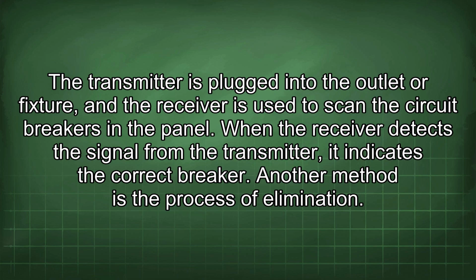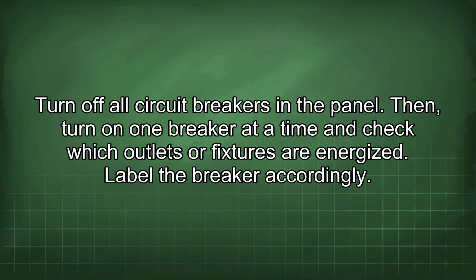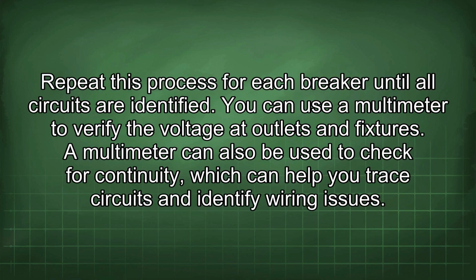Another method is the process of elimination. Turn off all circuit breakers in the panel. Then turn on one breaker at a time and check which outlets or fixtures are energized. Label the breaker accordingly. Repeat this process for each breaker until all circuits are identified. You can use a multimeter to verify the voltage at outlets and fixtures. A multimeter can also be used to check for continuity, which can help you trace circuits and identify wiring issues.